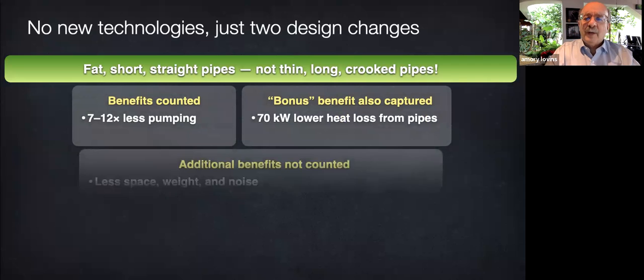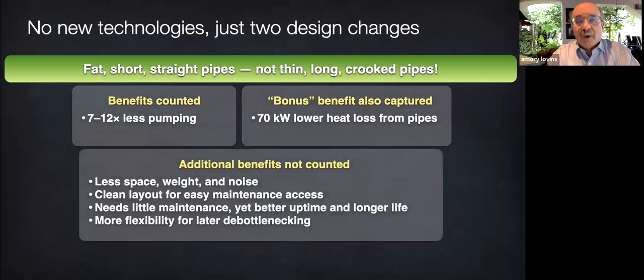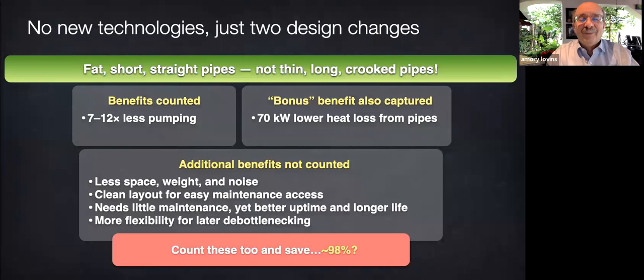But belatedly, I realized that we had left out 8 additional benefits we could have captured, each justifying even bigger savings. The system's more compact, it weighs less, it's quieter. Those all have a value. It has a wonderfully clean layout for easy maintenance access, reducing maintenance cost, but it'll need less maintenance anyway because there's less stuff to go wrong, so uptime will improve. The pipes will last longer without so many elbows being eroded by liquid turning the corner. And there's more flexibility for later debottlenecking if desired. I later estimated that had we properly counted and valued those extra benefits, we would have saved not 86 to 92% of the pumping energy, but probably nearer 98% with even lower capital cost. Indeed, in adding some piping in my own house, as you saw in the virtual tour, we saved about 97% of the friction and pumping power.